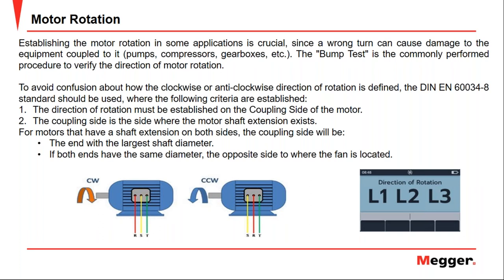For motors that have shaft extension on both sides, the coupling side will be either the end with the largest shaft diameter or, if both ends have the same diameter, the opposite side to where the fan is located. So we have to follow this instruction to know where the coupled side is. And then with the coupled side defined, we can decide if the motor is going to rotate clockwise or anticlockwise. In the end, we have to know which is the coupling side of the motor in order to determine the clockwise or anti-clockwise rotation of the motor.